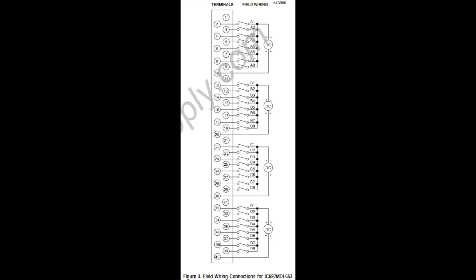What that means is this particular module is not sinking or sourcing. As long as the terminals 10, 20, 30, and 40 - in this case I'm using a negative 24-volt DC lead - are opposite of the channels you're probing, you're going to get a response. So I could have wired this the opposite way, with the positive lead going to 10, 20, 30, and 40, and probed with the negative, and I'd get the exact same response. So that's a little tip for you.